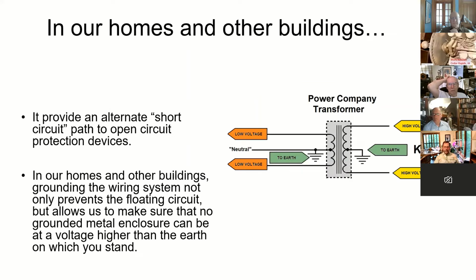The power transformer coming into your house typically has the center tap grounded on the supply side, and when it comes out to your house, they have it grounded at the pole so that it's not floating. It also makes sure that no grounded metal enclosure can be at a voltage higher than the earth at which you stand. So if you have a metal box, for example, and a hot wire short circuits to it, it will pull it down toward ground and hopefully trip a circuit breaker, so that you don't have a refrigerator or whatever that's 120 volts above the ground where you're standing. If you touch it and you're standing on ground or touching something like a water faucet, the current could go through you, if that makes sense.